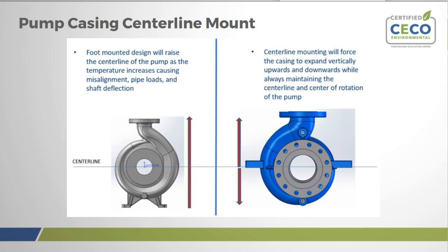So in this case, this is one of the reasons why ANSI pumps and foot-mounted pumps are generally rated lower temperature-wise than other, say, API-type pumps and other process pumps. Centerline mounting, however, when you look at the casing, the actual design of the casing is not any different. It's just where that casing actually is contacting the foundation. Of course, these centerline pads, as you can see, basically looking like ears on the pump itself. Those will be sitting on pedestals that they are then attached to the foundation or the base plate.